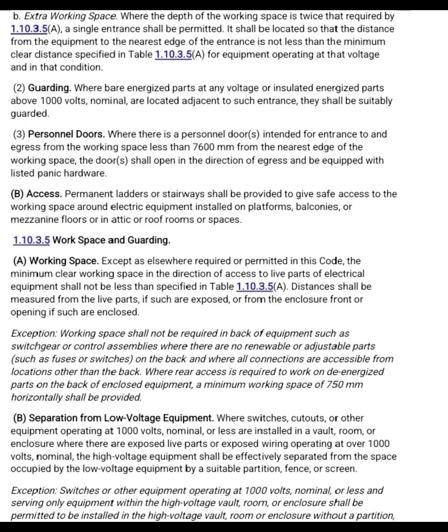Number 3. Personnel doors, where there are personnel doors intended for entrance to and egress from the working space less than 7600 mm from the nearest edge of the working space. The door shall open in the direction of egress and be equipped with listed panic hardware. B. Access. Permanent ladders or stairways shall be provided to give safe access to the working space where electrical equipment is installed on platforms, balconies, or mezzanine floors, or in attic or roof rooms or spaces.